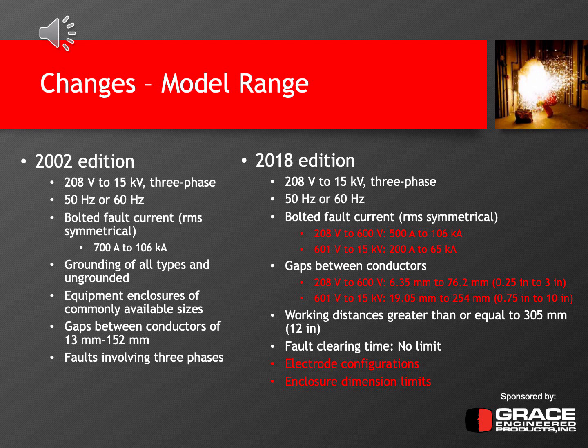So speaking of the voltage spectrum and some of the other changes in the model, the range has actually increased, and you can see from these two columns, the red text on the slide shows a lot of the changes versus the 2002 edition. In 2002, the model was applicable from 208 volts to 15 kV 3-phase, 50-60 hertz, and the fault current was from 700 amps to 106,000 amps. Equipment enclosures were commonly available sizes, and the gaps between conductors were set between 13 millimeters and 152 millimeters.